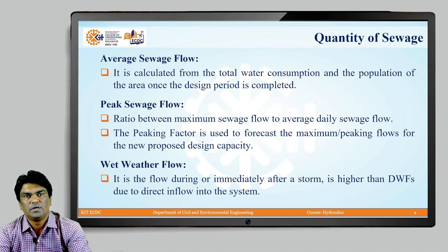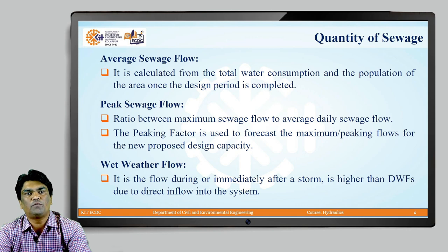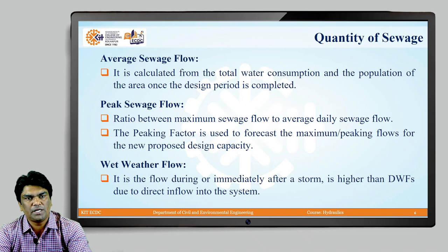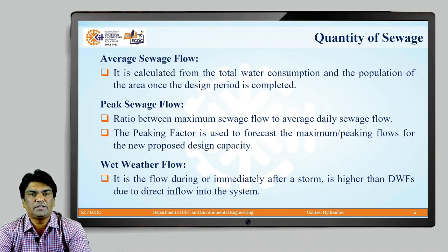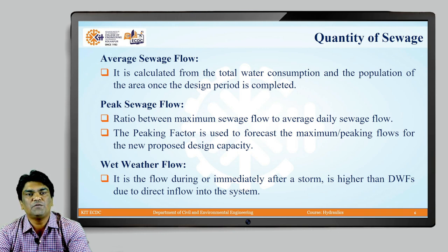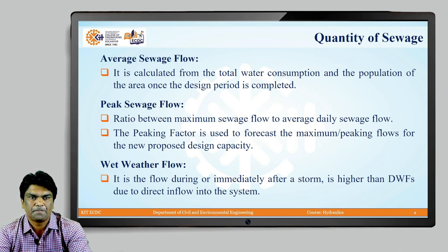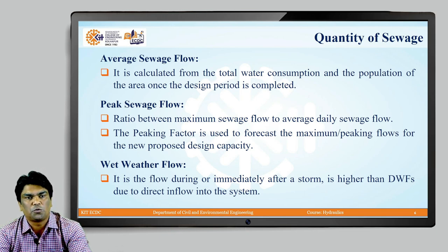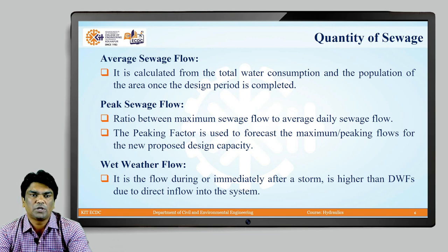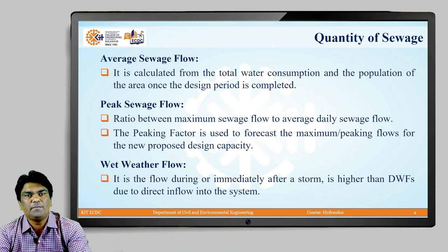Average sewage flow is calculated from total water consumption and population at the end of the design period. For example, for a town with a design period of 30 years, we identify the forecasted population after 30 years, then find the average demand — say 150 liters per capita per day — and multiply by the forecasted population, say 1 lakh. Out of the total water quantity, 70 to 80 percent is converted into sewage, giving the average sewage flow.